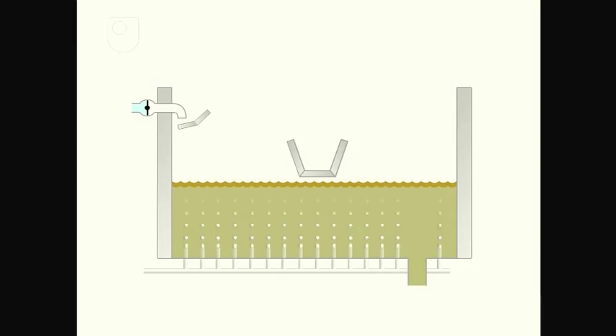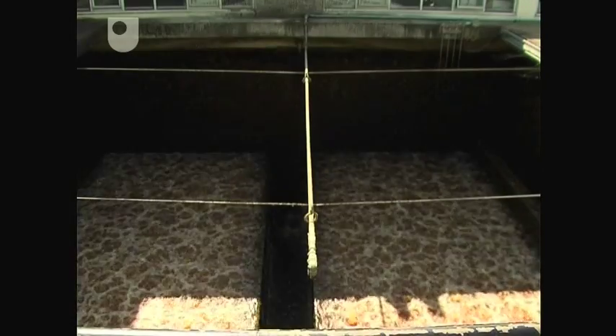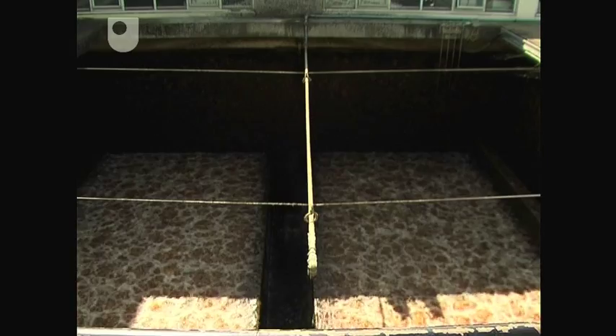Air is then pumped up through the one metre thick sand filter. This produces a scouring action and any accumulated solids in the bed are dislodged and rise to the surface as scum.